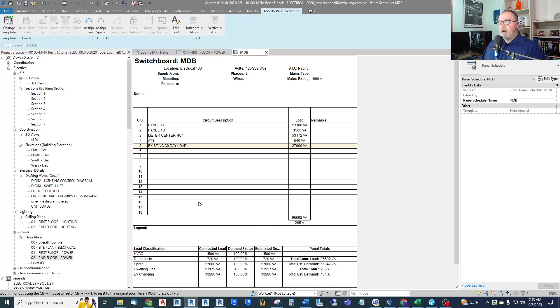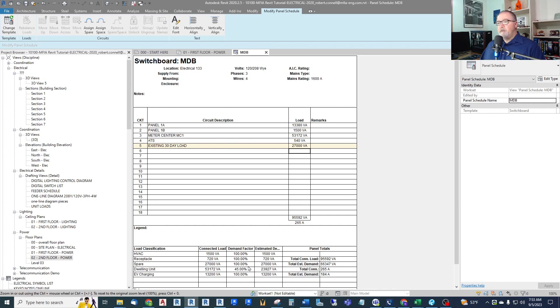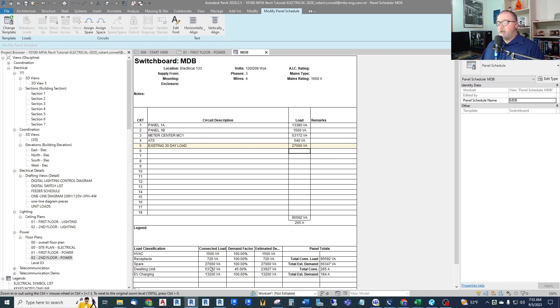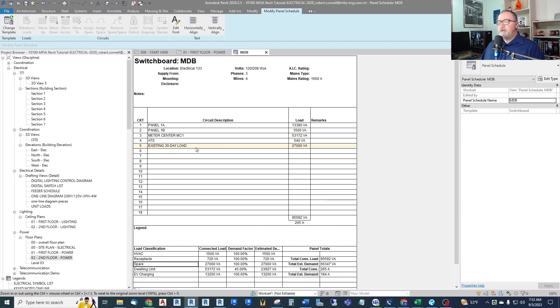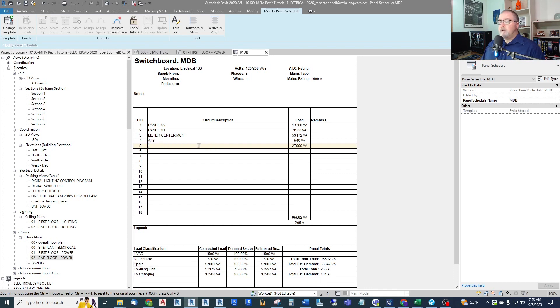That's in there and it adds up at the bottom, but under load classification it just shows spare and it applies it at 100%. Typical existing loads like that, NEC makes us take those at 125%. So we have to apply the proper NEC rule so you can't change that and you can't change the category. So that way it's not great if you need to itemize the load or apply demand factors.